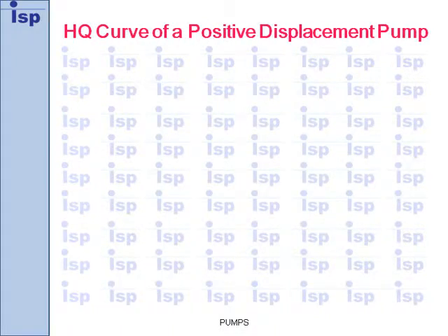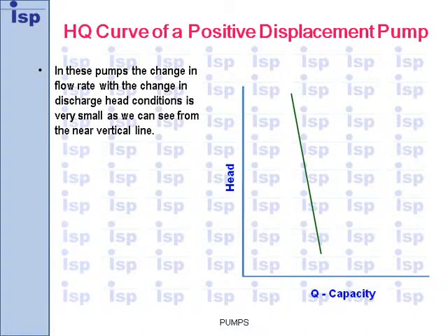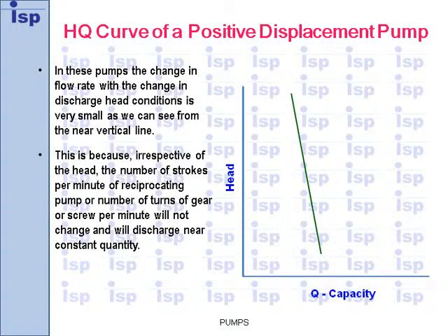HQ curve of a positive displacement pump. In these pumps, the change in flow rate with change in discharge head conditions is very small, as we can see from the near vertical line. This is because, irrespective of the head, the number of strokes per minute of a reciprocating pump or number of turns of a gear or screw per minute will not change, and will discharge a near constant quantity.